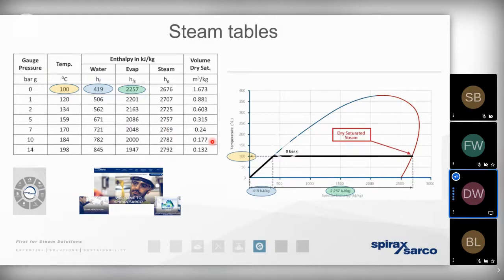So it's important to understand that when steam gives up its heat energy at the process, it condenses. It changes state from a gas to a liquid. It's actually only the enthalpy of evaporation, that's the energy that is passed across the thermal barrier and into the process. So that means that the energy that's left behind in that liquid condensate, the byproduct, is exactly the same as the sensible heat or the energy that we added into that boiling water to make it evaporate.